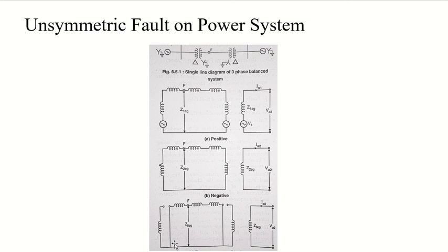And because of that, the net fault current will be the fault current considering the system under no load condition, and then you add the load current, which is superimposed over the fault current. So by that way you can find it.